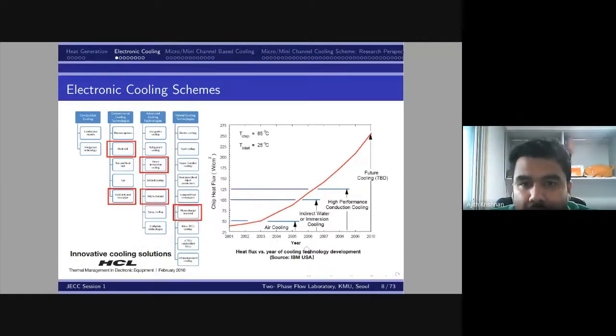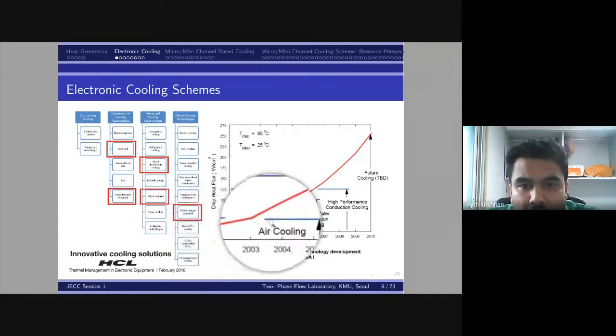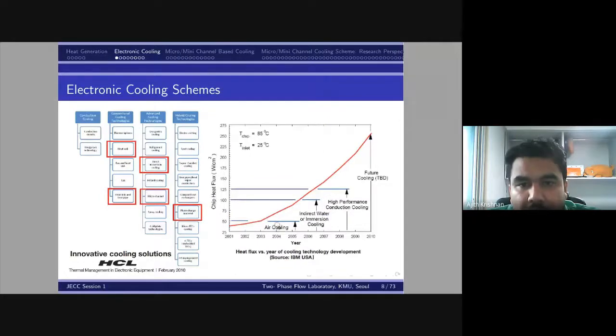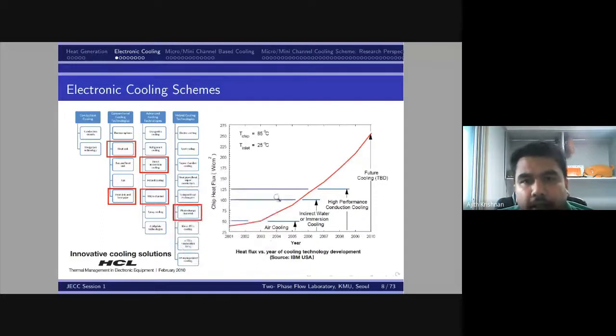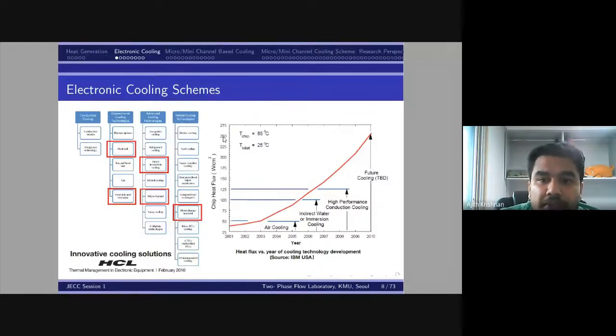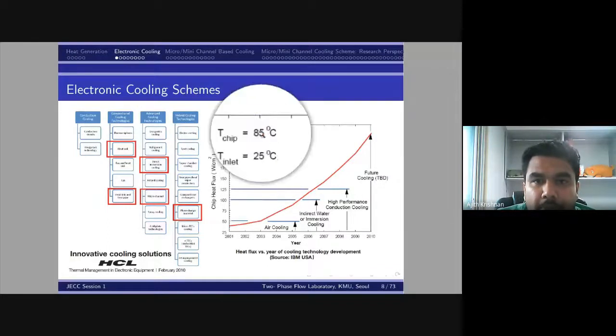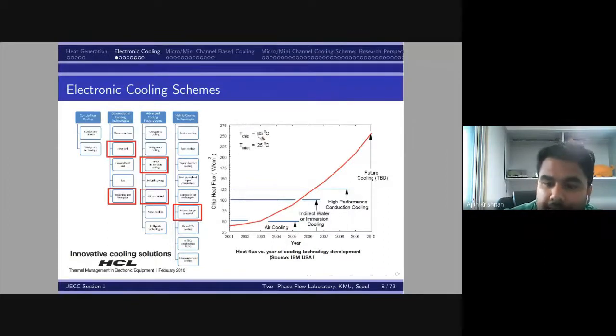This is a graph showing how much heat flux can be removed by different cooling technologies. You can see basic air cooling, which is used in normal desktops, where a fan runs and a heatsink is present. It can carry heat only up to 50 watt per centimeter square. High technology future cooling devices can dissipate up to 250 watt per centimeter square, maintaining chip temperature at around 85 degrees Celsius.